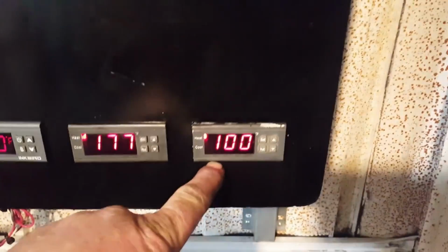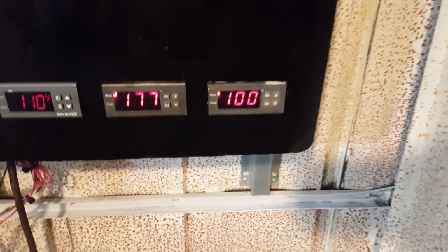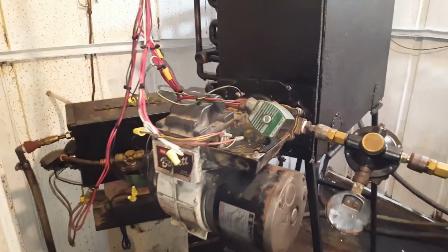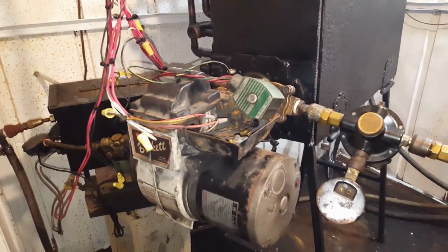As you can see, my water temperature is already up to 100 degrees. She's rolling a little smoke right now, but I expected that with all that oil in the burner tube. I don't know if you can see smoke rolling out of the building, but it's rolling pretty good. I'm going to let it run for a little while and burn all that oil out and see what happens.